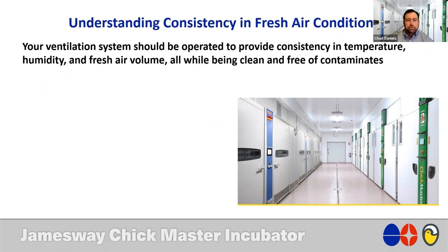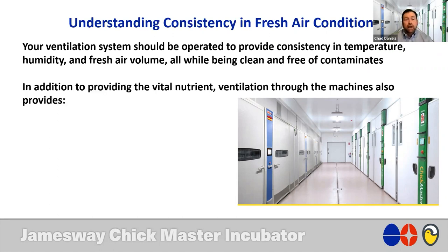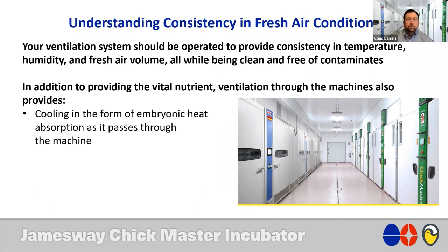Your ventilation system should be operated to provide consistency in temperature, humidity, and fresh air volume, all while being clean and free of contaminants. In addition to providing the vital nutrient, ventilation through the machine also provides cooling in the form of embryonic heat absorption as it passes through the machine. So when we design machines, we design with that particular concept in mind. We understand that we have to have the airflow for oxygen, and therefore that cooling that occurs is also a part of the design of that machine.